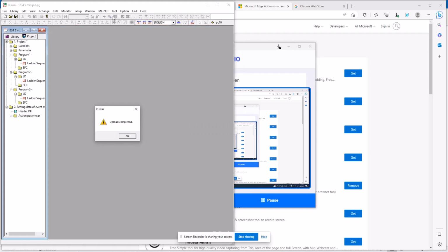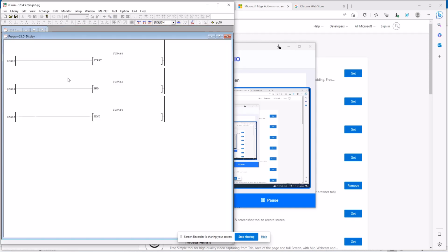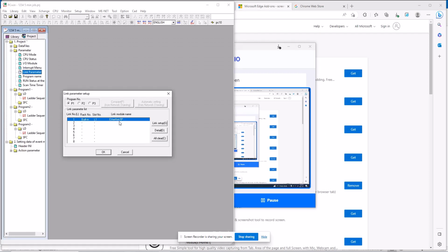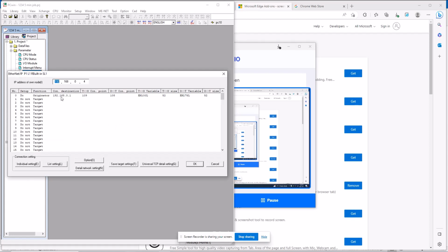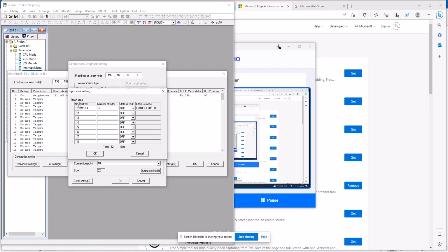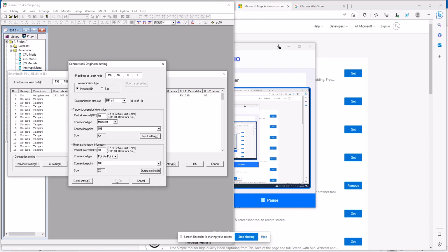We've already got this one set up, so we're just going over what it takes to set it up. After we've set up Ethernet IP connections on built-in Link 1, then we'll go to Detail. You see we've got our IP address there for the SIG350, our instance IDs, and we're doing 52 bytes consume and produce, and it will be going to EM100 to the low byte.